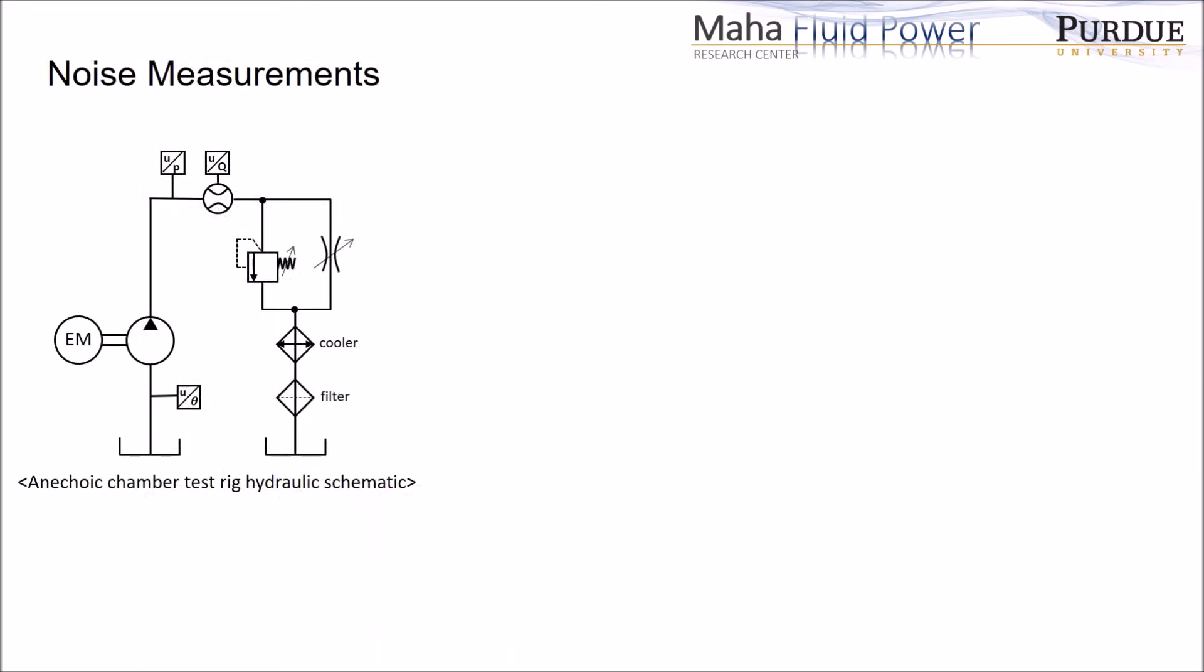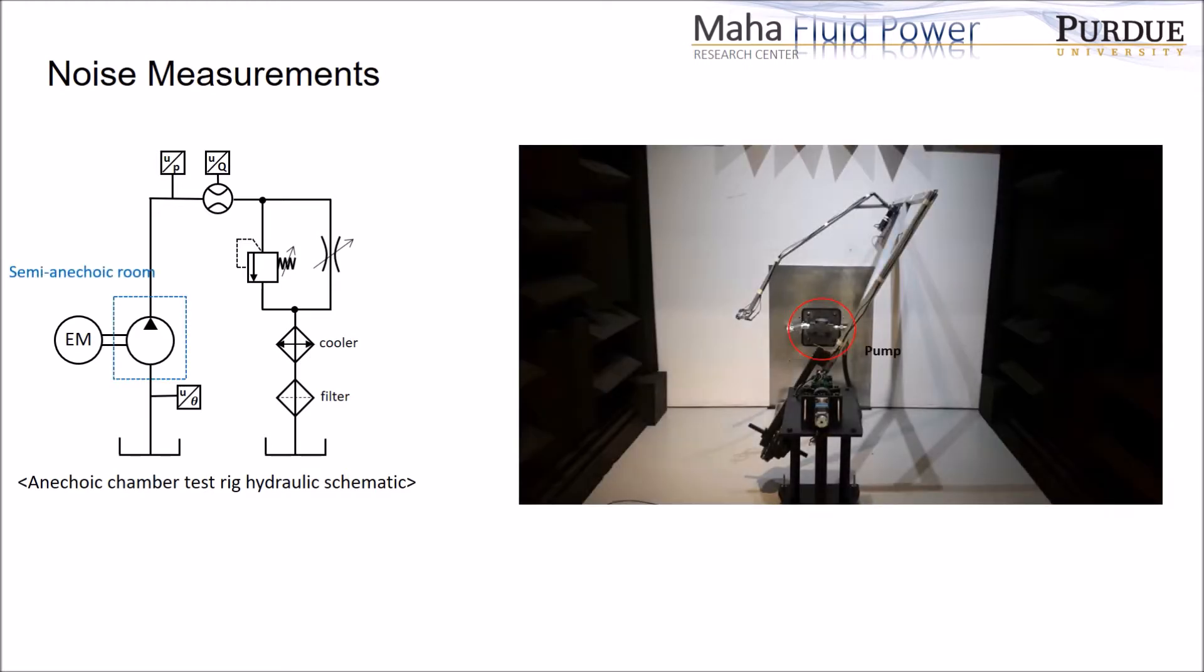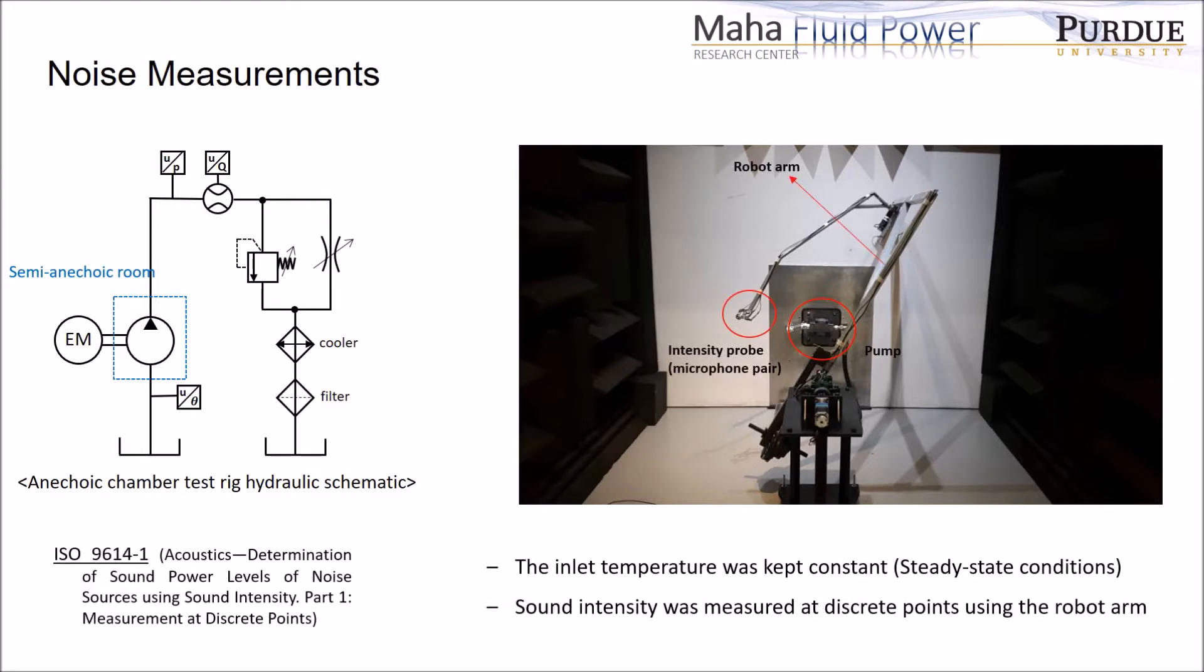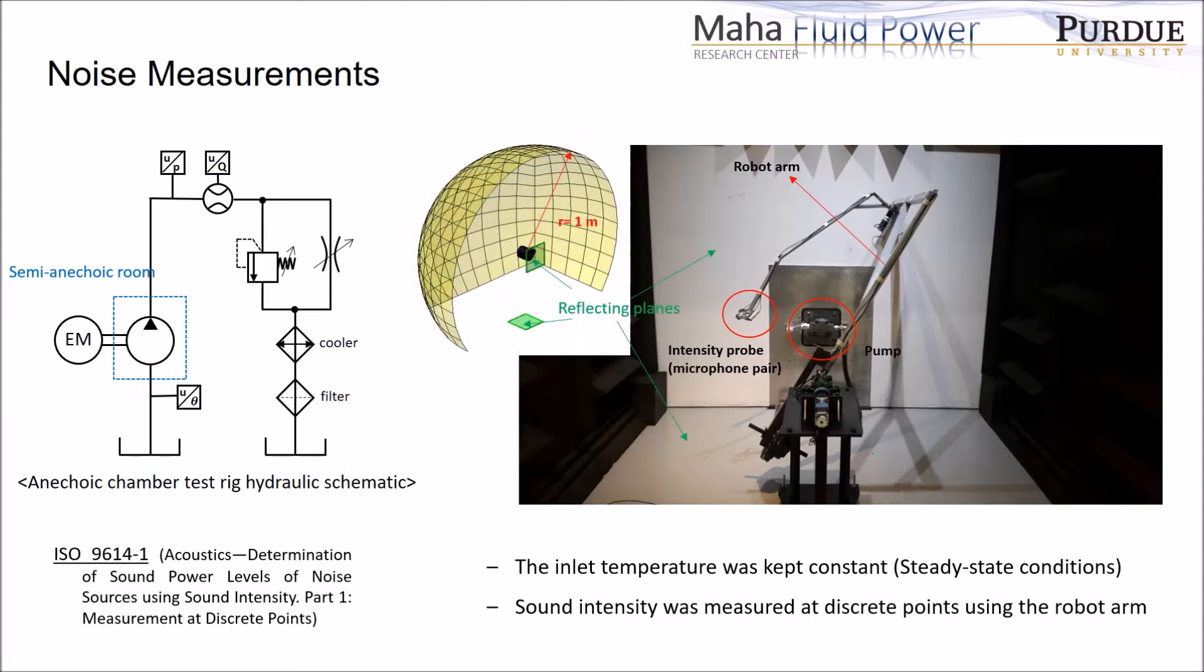To validate the acoustic model, the pump was tested at the semi-anechoic chamber. Only the pump and the short connecting lines were inside the chamber, and during the measurement, the temperature was kept constant. Sound intensity was measured using the robot arm following the ISO standard. To be specific, the robot arm moved the sound intensity probe to the desired point, and the noise was recorded for a few seconds. Then, the intensity probe was moved to the next position. The shape of grid points for the measurement is the same with the shape of the field point mesh, and you can also see the two reflecting planes, which are the wall and floor inside the chamber.